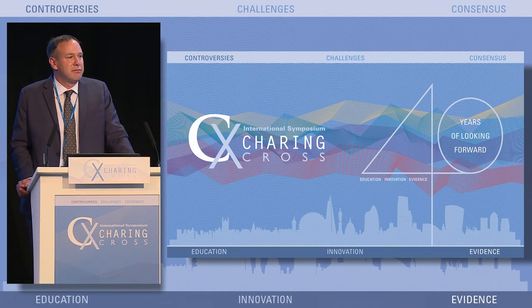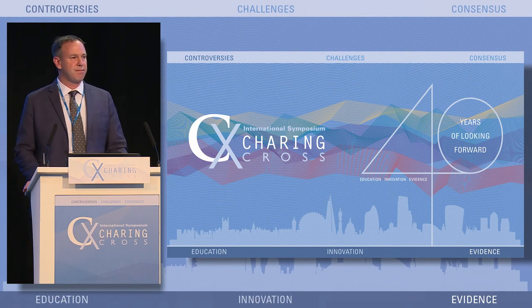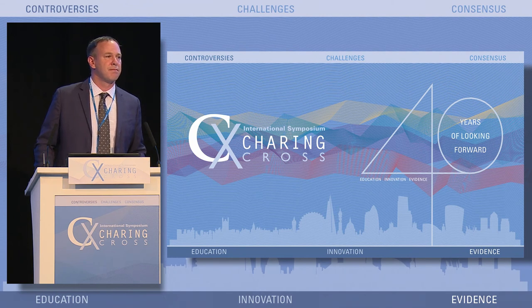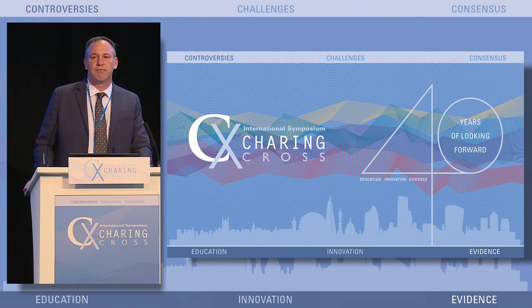Hi, I'm John Pickett from Ohio — founder and chief medical officer of VentureMed, who created this device. Dr. Deaton, to answer your question, we chose the blade height for two reasons. Number one, regulatory: because of their predicates, we didn't want to be taller in height. Second, it's very important — as some studies show — that height allows you to avoid contact with the elastic lamina. There's a lot of data coming out that if you do injure or perforate that elastic lamina, it's one of the contributors to restenosis. Thank you very much for this additional explanation.